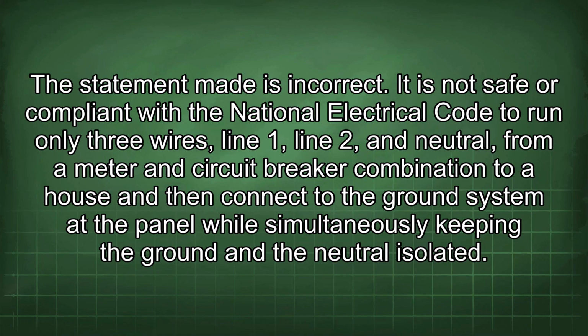The statement made is incorrect. It is not safe or compliant with the National Electrical Code to run only 3 wires, line 1, line 2, and neutral, from a meter and circuit breaker combination to a house and then connect to the ground system at the panel while simultaneously keeping the ground and the neutral isolated.